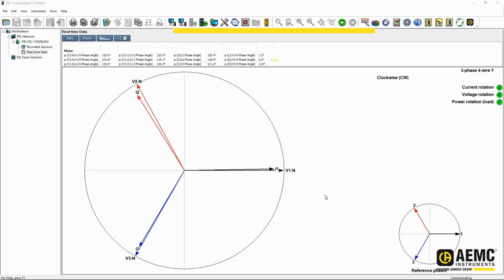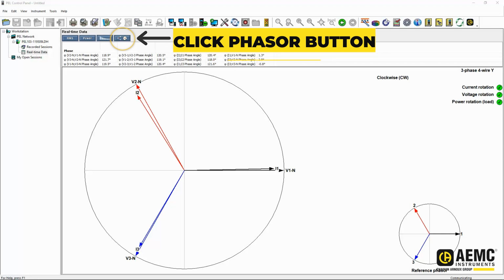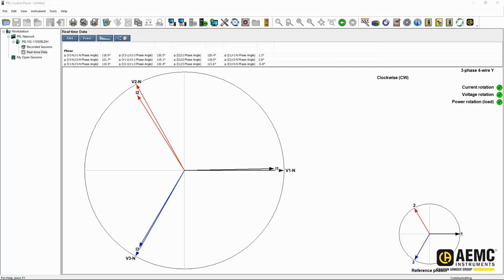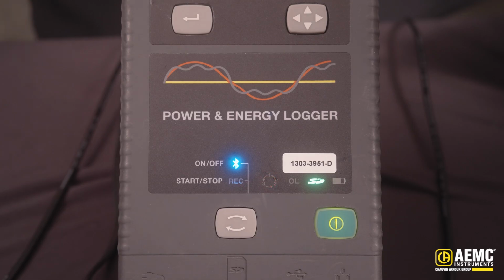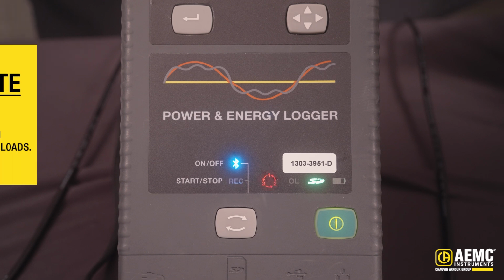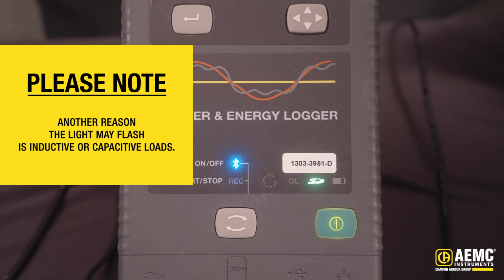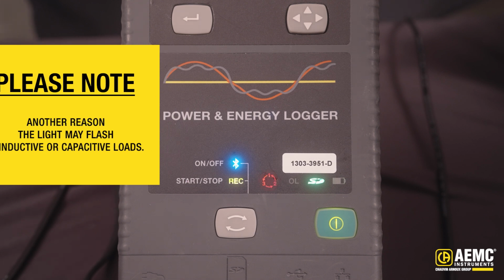The phasor can be used to troubleshoot my current sensors and voltage probes if they're oriented wrong or installed out of order on the instrument. The phase order light indicates that there is a potential error with how the sensors are hooked up or the phasing of the panel or system that's being monitored. If you see this light flashing, simply observe how your sensors are installed and correct the issue if necessary. Also, it's worth noting that sometimes this light will flash if there's not enough current present on the sensors.